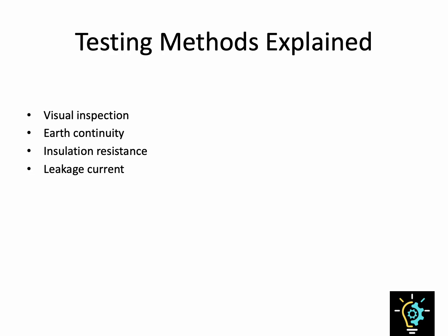When it comes to the actual testing methods, IEC 62353 defines several. Visual inspection always comes first. We check the cables, the housings, and the connectors for wear and damage. Then after this, we check the protective earth continuity. We make sure that the grounding is always intact. And insulation resistance testing is optional, but it is recommended.